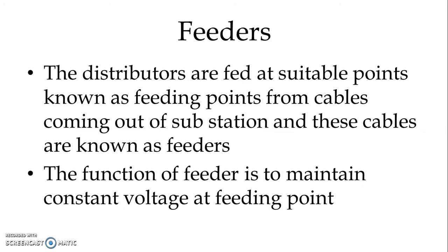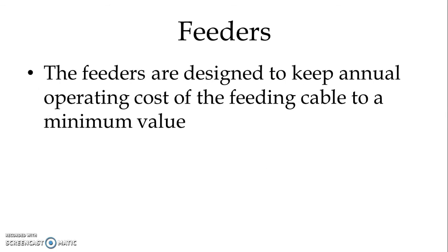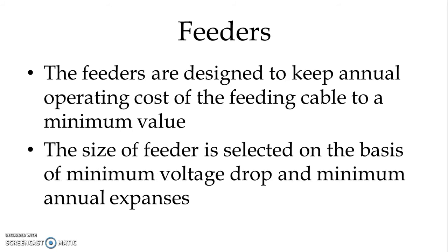The function of a feeder is to maintain constant voltage at the feeding point. The feeders are designed to keep annual operating costs — which include losses, interest, and depreciation of the feeding cable — to a minimum value. The size of the feeder is selected on the basis of minimum voltage drop and minimum annual expenses.